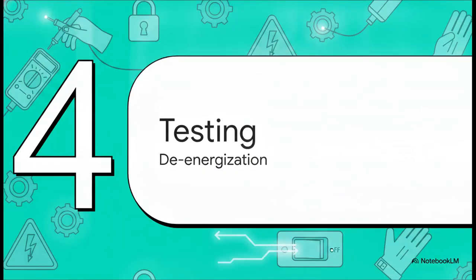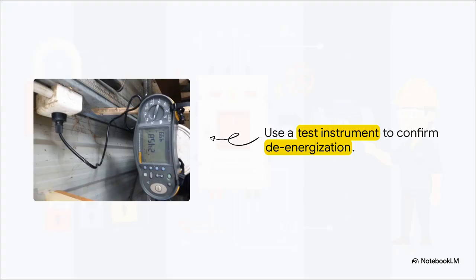Which brings us to Section 4. Testing for de-energization. Keep in mind that under electrical safety regulations, the act of testing itself is legally classified as energized electrical work, so it requires your absolute 100% focus.